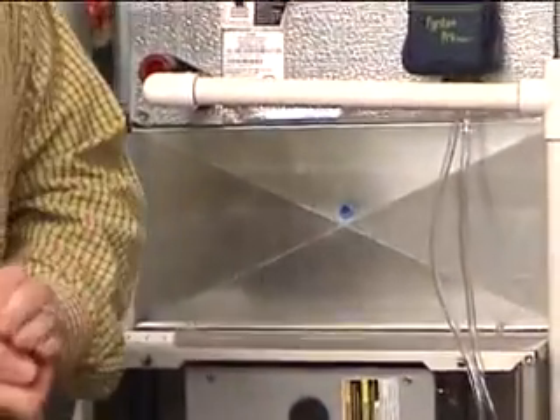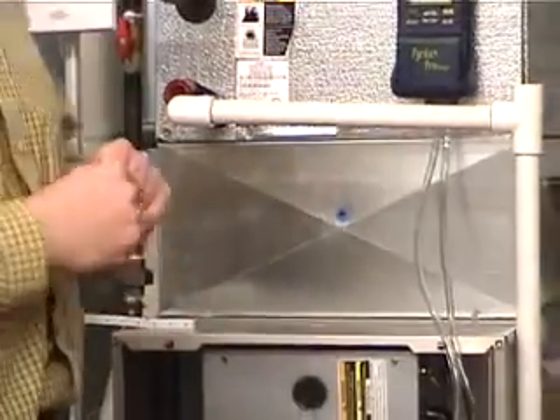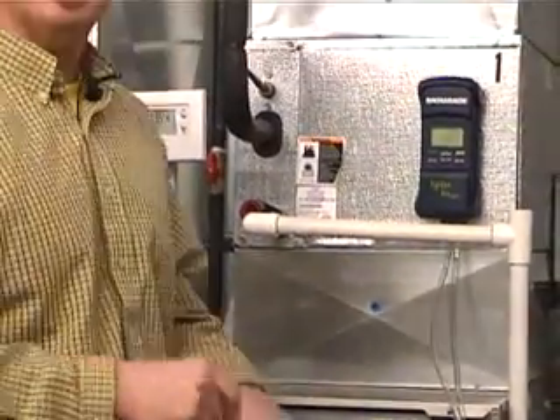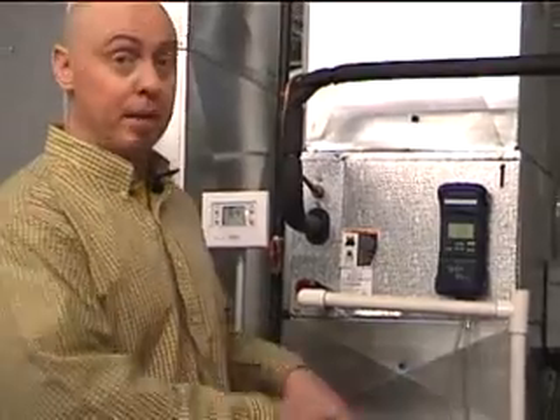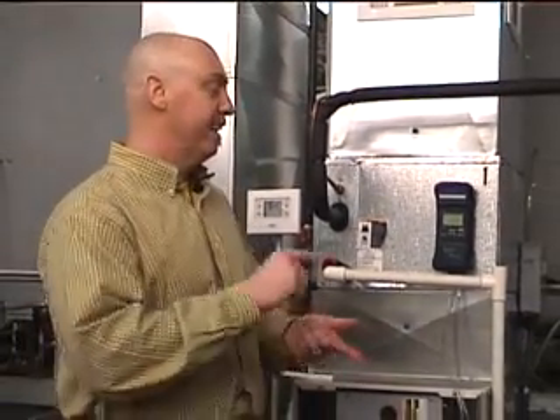And I also recommend, when you go out, it's one of those measurements that should be taken all the time. When you look at the nameplate, if the manufacturer went through the effort of stamping it on that plate, it's pretty important to check. You should be checking the gas pressure, the temperature rise, the voltage, and doing a complete analysis on the efficiency, including combustion testing, so you know that the equipment is safe in operation and operating properly. Know that your CO is correct. Know that your O2 is correct, and your combustion efficiency.